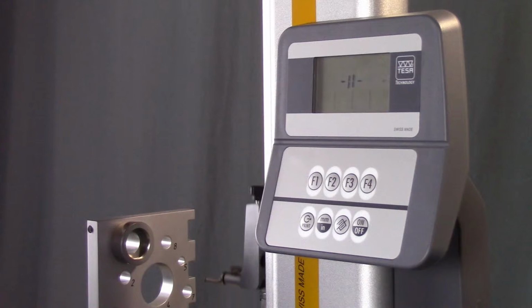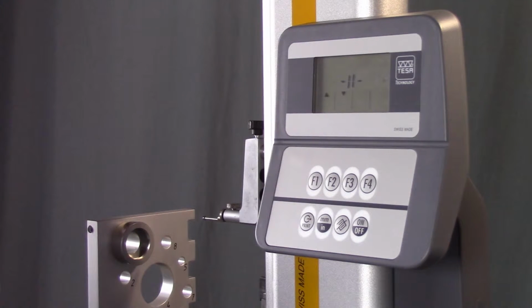Slowly move the measuring head up until you see two triangles appear on the display. Once these arrows are displayed, you can start bringing the probe down the column. Continue bringing the measuring head down until Start 1 is displayed. The tool is now in measuring mode and ready to calibrate.